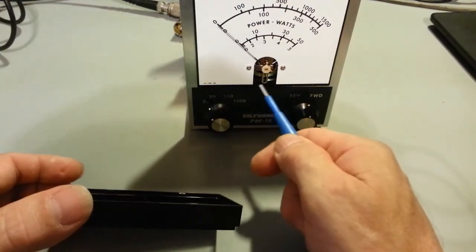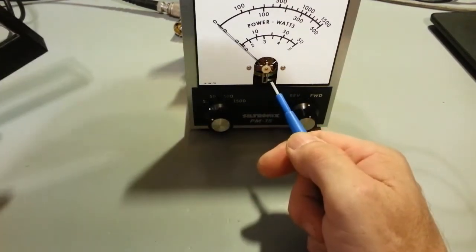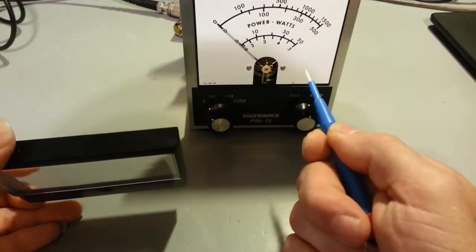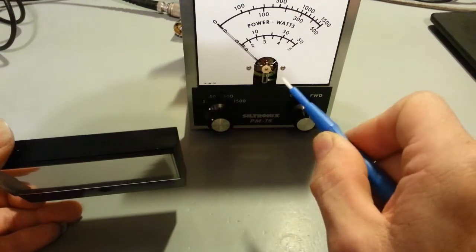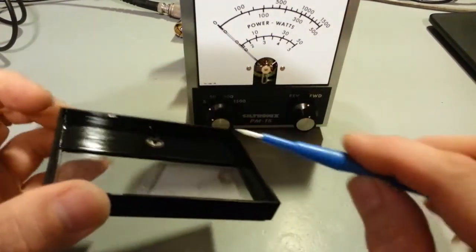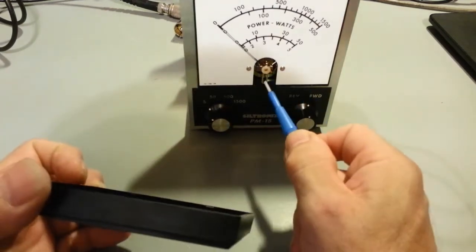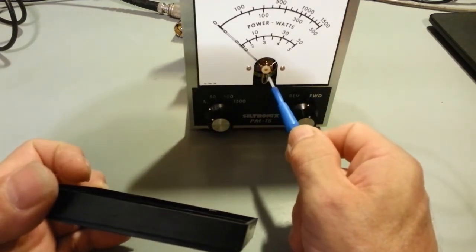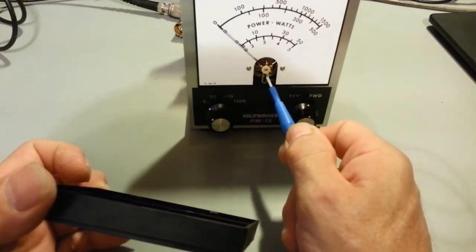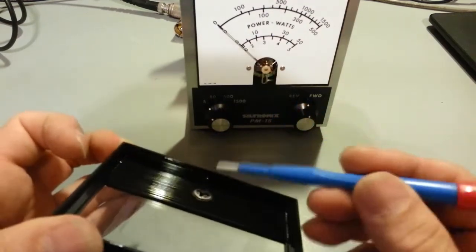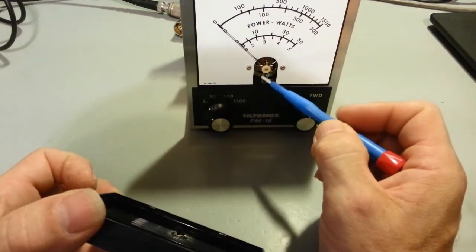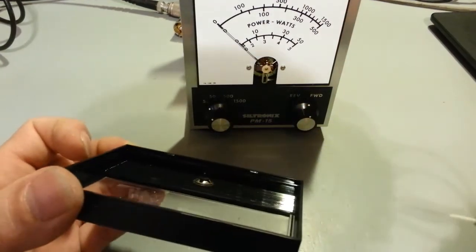Now, if it gets on the outside edge, one side or the other, not a big problem usually. You'll turn it and it'll move the needle in one direction or the other. But then when you keep turning, it won't go back in the other direction. So you'll just have to pop the face off. Now, the problem is if you get that pin and it lands on the little metal that comes down on either side here. Like I say, that's an oval. If it pushes in on that, you can bend this part. Or I've even seen in some meters where that's really heavy metal right there. This little U bracket, I guess you could call it. And the pin will break off.